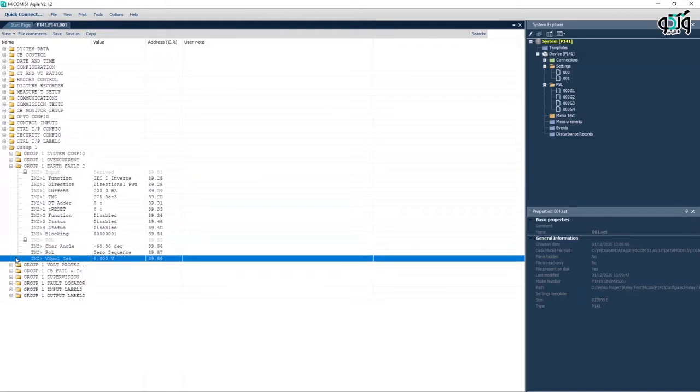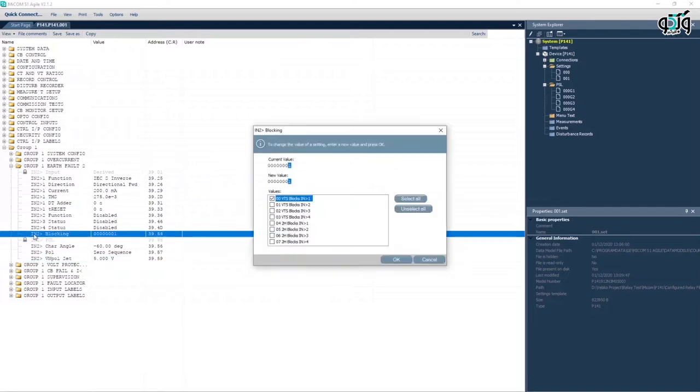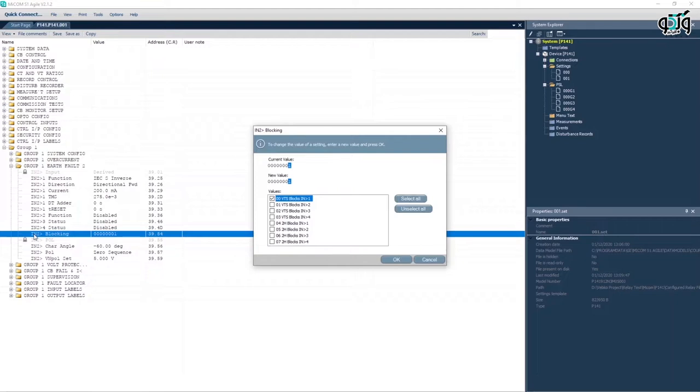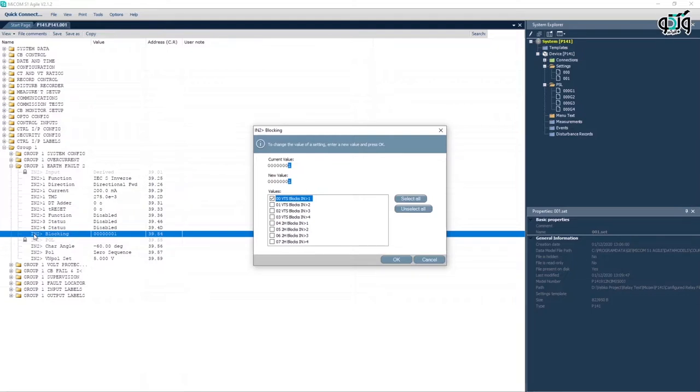It is possible to use the voltage transformer supervision element to block the performance of directional residual current element. This is done in IN2 bigger than blocking cell. If number 1 is selected, the VTS blocks the performance of directional residual current. If number 0 is selected, in case of VTS performance, the stage turns into a non-directional stage.